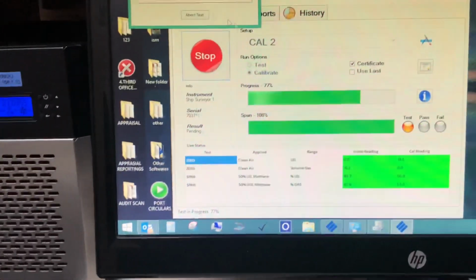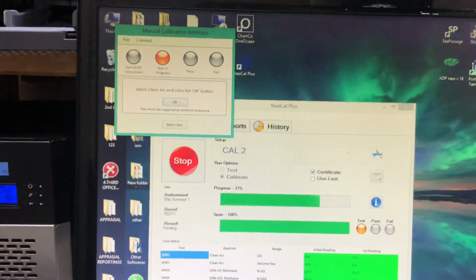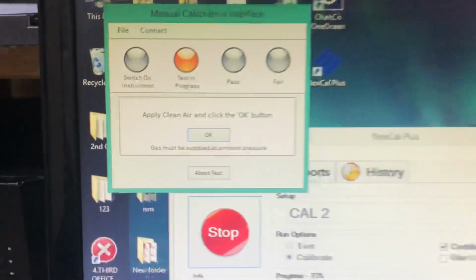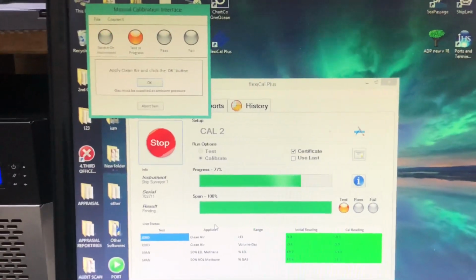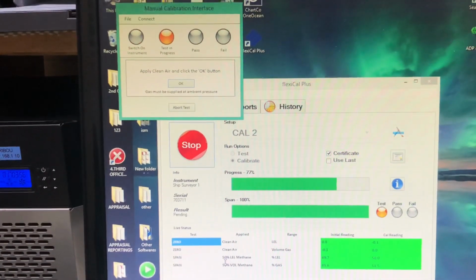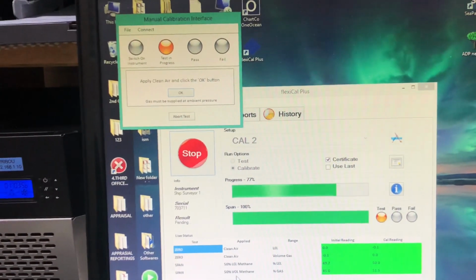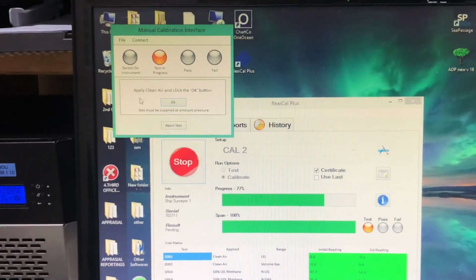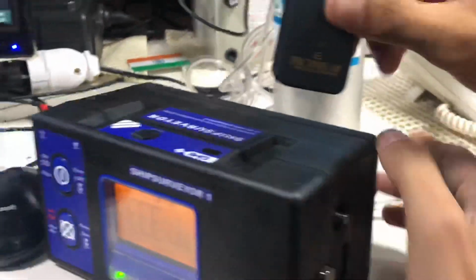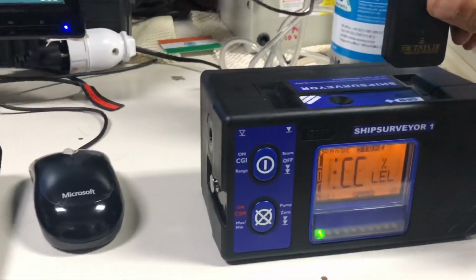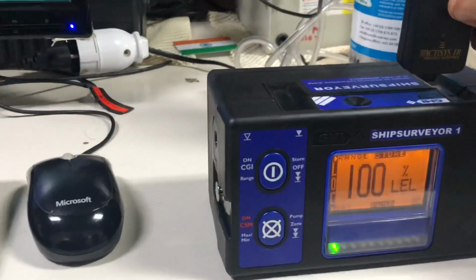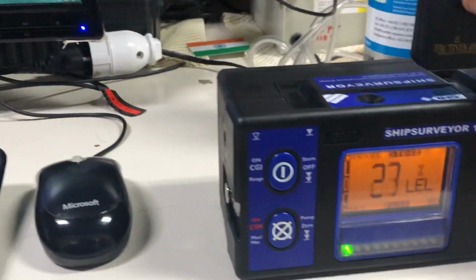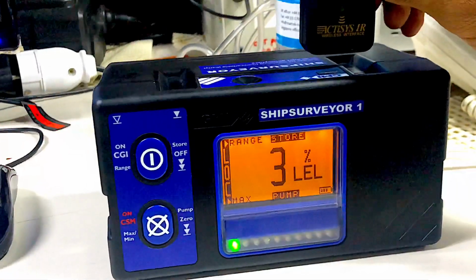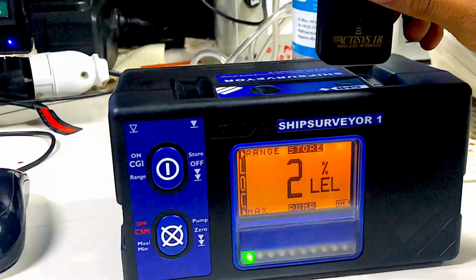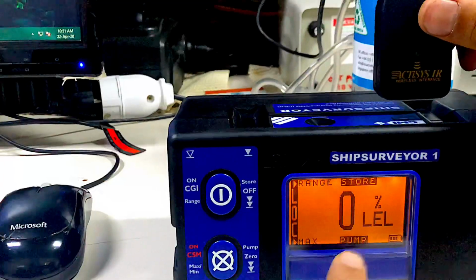So now after the application of the second gas, that is 50% volume methane, the final step is to apply the clean air. Once you have successfully applied both the gases, first 50% LEL and then 50% by volume methane, the final step is to apply clean air. So now we remove the gas tube from the instrument. As you can see, it's showing 0% LEL.